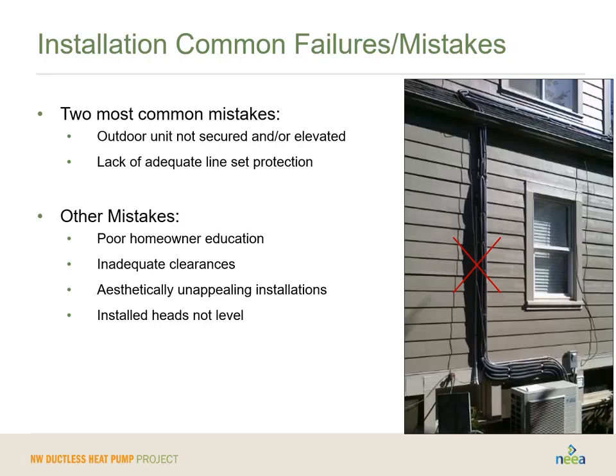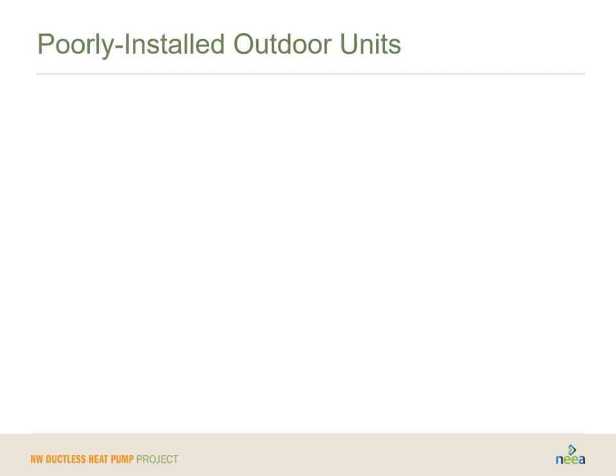Again, these other mistakes, that poor homeowner education that I mentioned, not having good clearance around the device, really having aesthetically unappealing installations, and in general, not installing the heads level on the interior. We see these on a pretty regular basis, and it's usually because people are moving quickly and trying to get that best price for the homeowner. But if you have to come back to fix the job, you didn't give them the best price. So here I'm going to go through some examples of some poorly installed outdoor units and then some poorly installed indoor units.